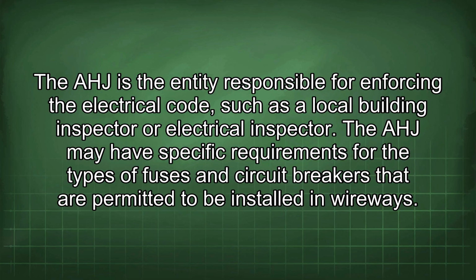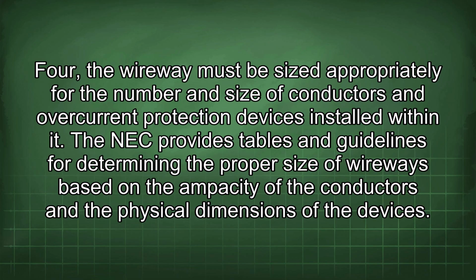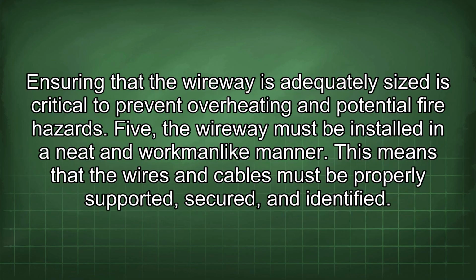in wireways. 4. The wireway must be sized appropriately for the number and size of conductors and overcurrent protection devices installed within it. The NEC provides tables and guidelines for determining the proper size of wireways based on the ampacity of the conductors and the physical dimensions of the devices. Ensuring that the wireway is adequately sized is critical to prevent overheating and potential fire hazards.